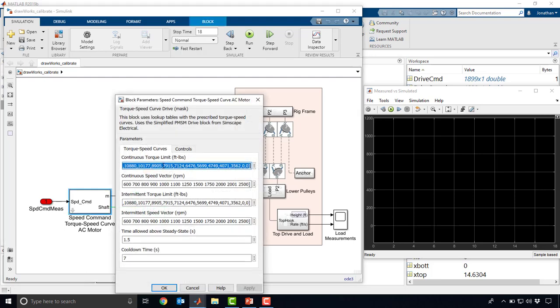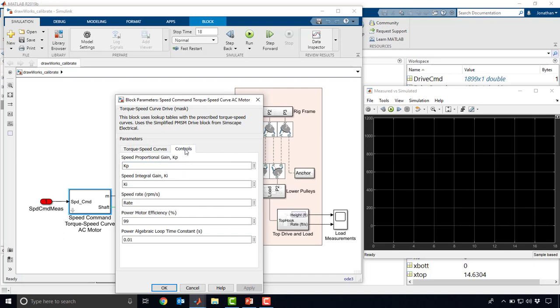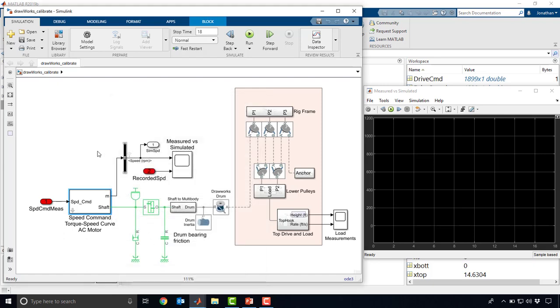What we've actually done is parameterized this model using our best guess for the field equipment. This involves our torque speed curves that we have from our data sheets, and then our guesses for controls. So KP gains, KI gains, we didn't have access to these parameters, speed rate, the ramp up and down rate that we have for this drive. We've basically parameterized this with our best guesses.